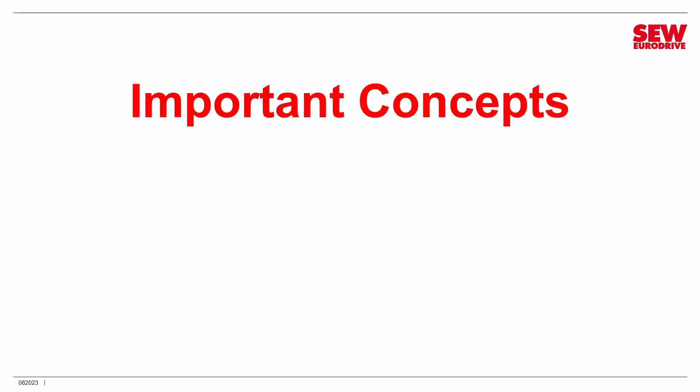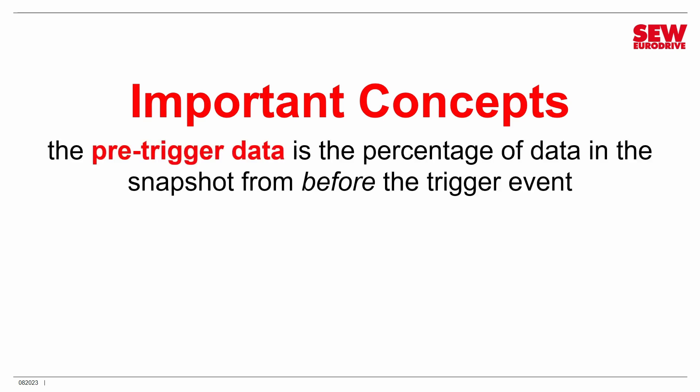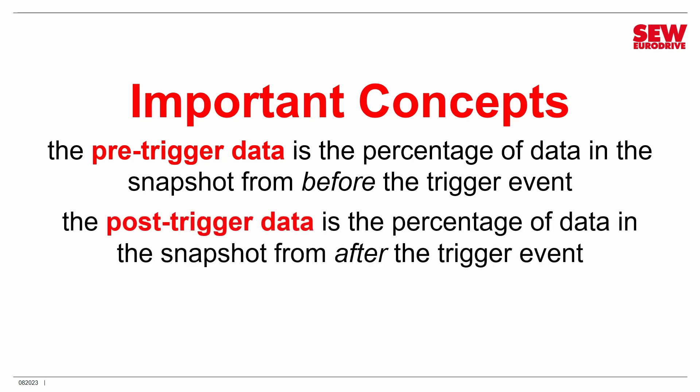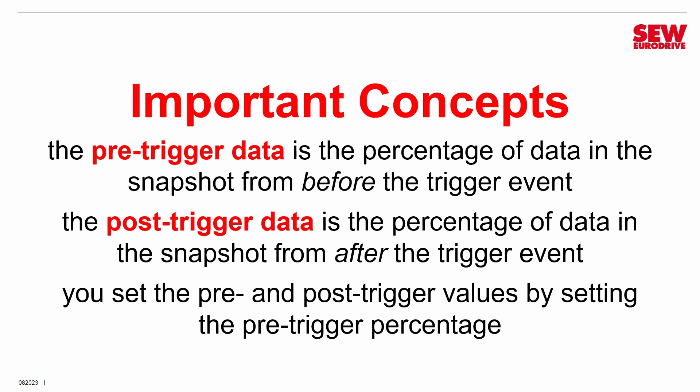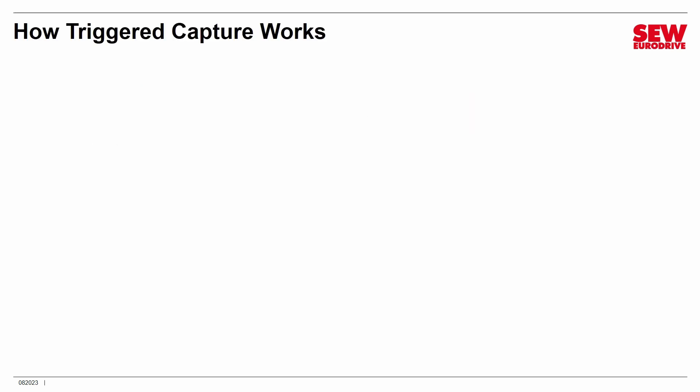Some very important concepts: the first is pre-trigger data — the percentage of the total snapshot from the time before the trigger event, meaning information from the channels before the trigger happened. Then there is post-trigger data — the percentage from after the trigger event. Pre- and post-trigger data surround the trigger event. You set the pre- and post-trigger values by setting the pre-trigger percentage only; the post-trigger percentage is whatever's left. So if you set the pre-trigger to 10%, the post-trigger is automatically 90%, because they must add up to 100%.